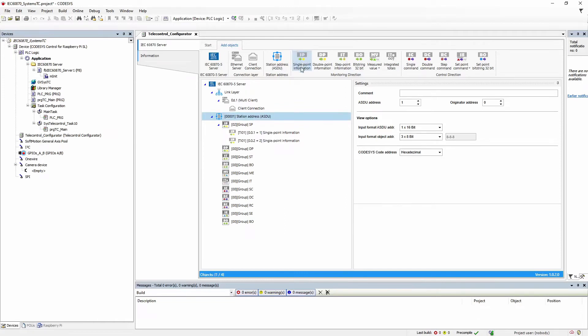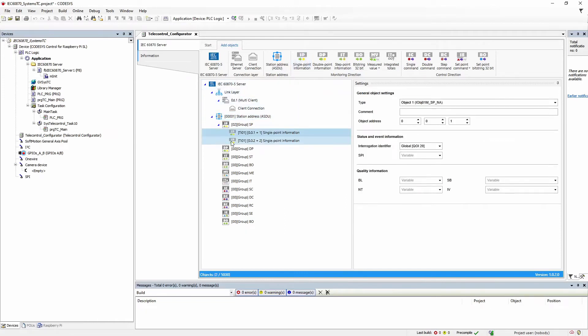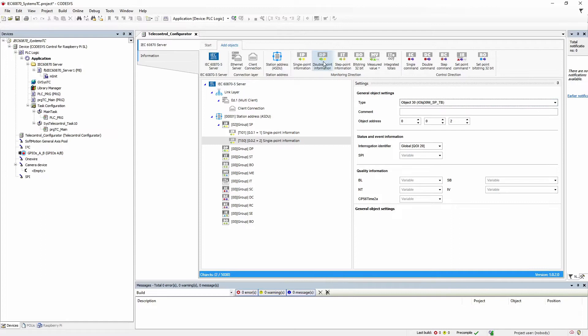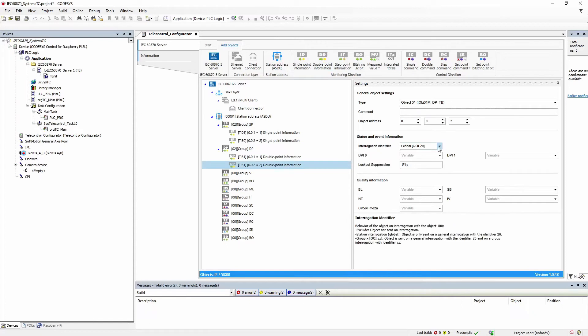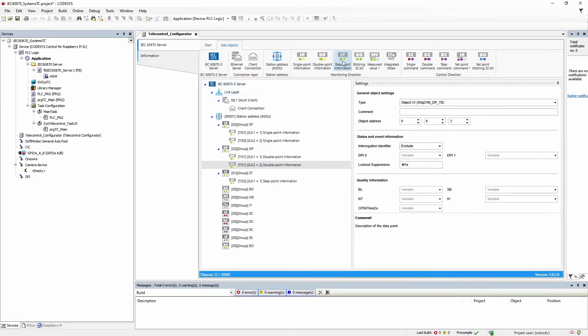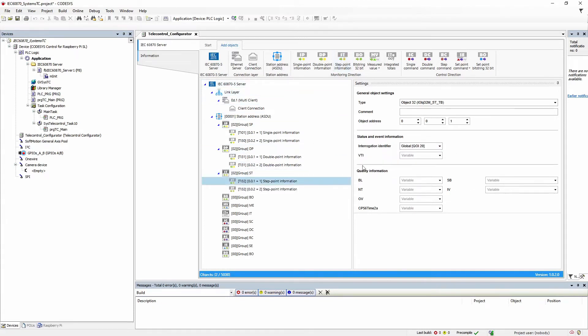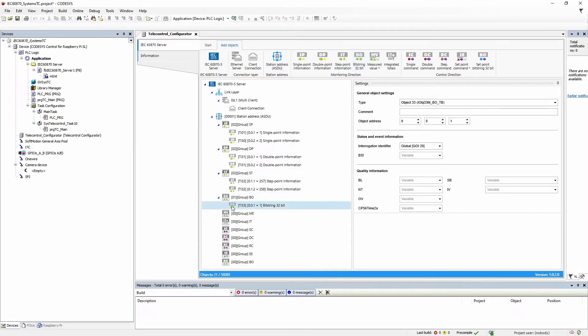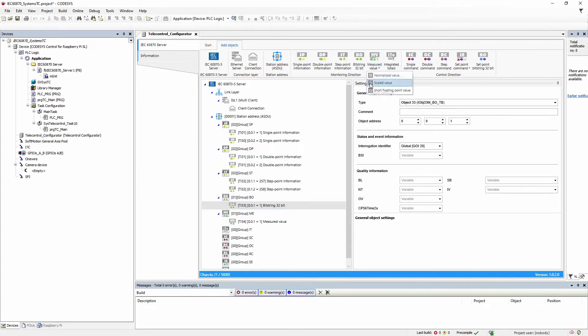Let's create several objects — for example, two single point information objects, the first of type 1 and the second of type 30; two double point information objects, of which the second one shall be excluded from the interrogation; two step point information objects with adjusted object addresses; one bit string object; and three measured value objects regarding the types normalized value, scaled value, and short floating point value.